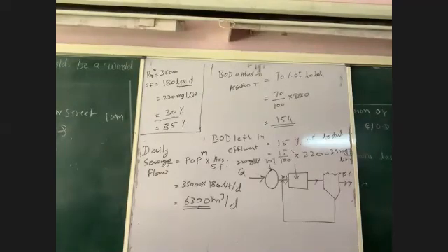What is the CI value? It is 154. And what is the CE value? It is 33. So 154 minus 33 upon 154, into 100, and you may get the answer, 79%. This is the actual efficiency of your activated sludge treatment process.